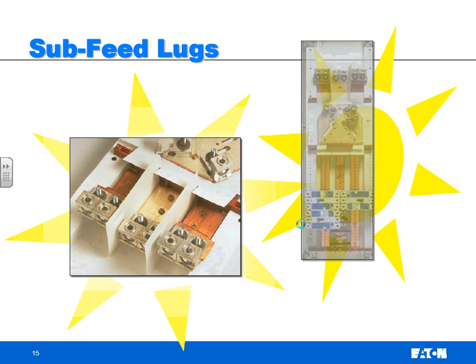Physically, this is what it's going to look like. You may have a 100 amp panel rated for 1 cable per phase incoming, and you'll put 2 lugs on there. And this is a mechanical lug. If you see, that's another thing to point out, I guess. Mechanical lugs are these screw types that you're seeing here. So you can take the lug, put it basically in a hole for the lug, and then screw down the terminal, and that tightens on the copper to make the connection. The other method is the compression lug, where you actually take a metal device over the end of the copper, and that metal device will have the termination on the other side, and you crimp that down tightly to make your connection.